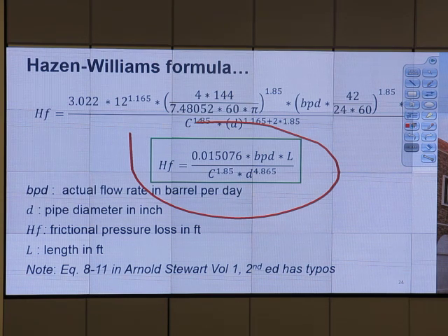Let's say you use the Hazen-Williams equation and you find that, okay, pressure drop is 20 psi. They use their calculation with oil and they tell you pressure drop is 20 psi. Now is the time for you to question that. Because if you use oil, let's say oil has a viscosity of 10 centipoise, water is just 1 centipoise, right?